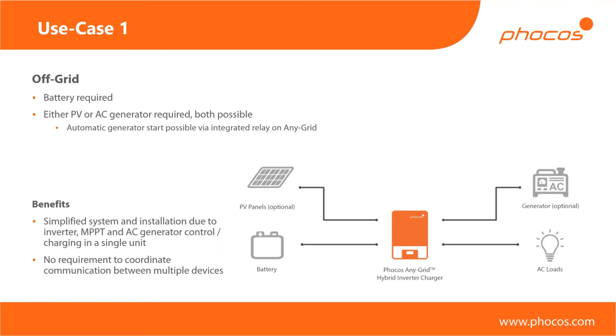So you cannot really compare this to a straight feed-in inverter, where it's vital to have anti-islanding to not inadvertently create an island when the grid has failed. That's not really comparable here, because when the grid does fail, or when the grid goes down, then the device automatically switches over to off-grid mode, which by definition is an island.